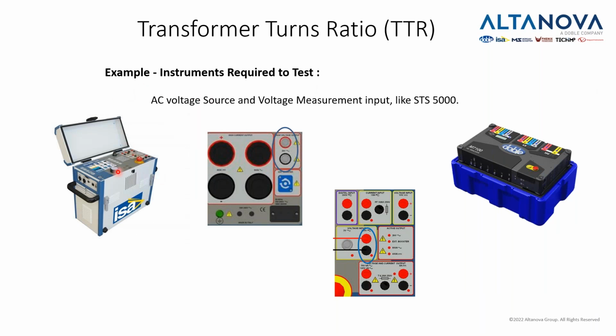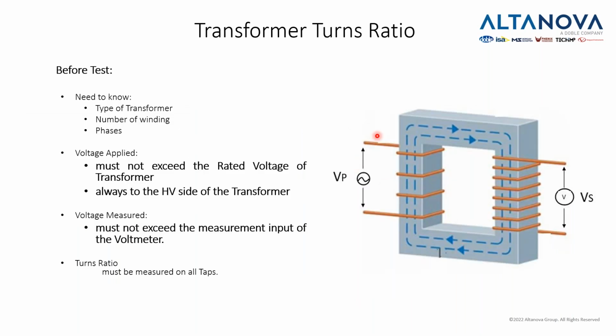In order to do such a test, you can use a single function or a multifunction test set, in this case STS 5000 or M7100, which you can see here, and you would need to generate a voltage on the primary side. Always generate on the primary side and measure on the secondary side, because that way you don't need a device to measure very high voltages. If you were to generate on the secondary side and measure on the primary, we would need to have a voltmeter which could measure up to a few kilovolts.